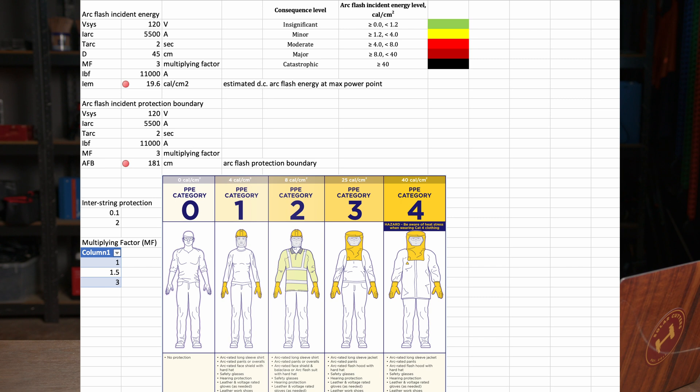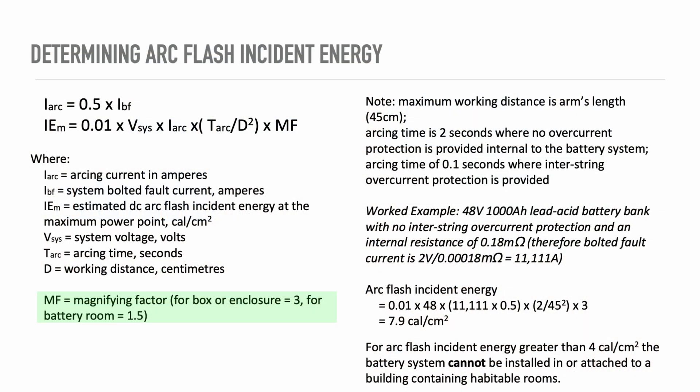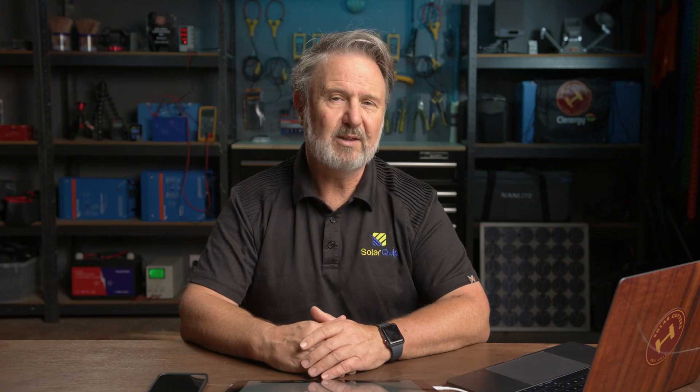I've got a spreadsheet here that puts the formulas from the standard into a spreadsheet. You change only the variables: battery system voltage, bolted fault current, arcing time, and the multiplying factor. The multiplying factor accounts for enclosing an arc within a confined space, which multiplies its intensity. In open air the multiplying factor is 1; in a room it's 1.5; and within an enclosure — such as opening the doors to a battery system — it's 3. It's really important to get that right.